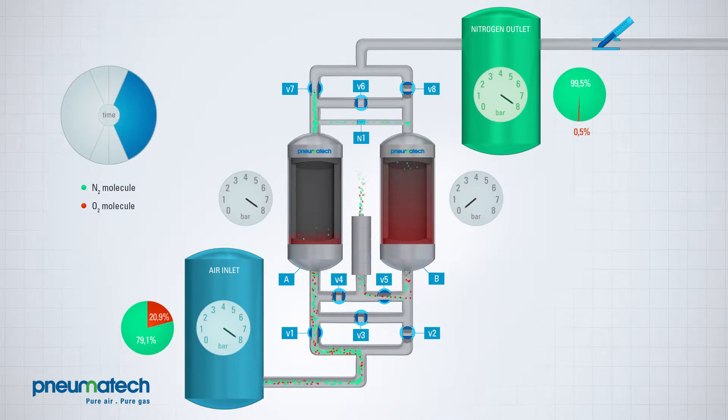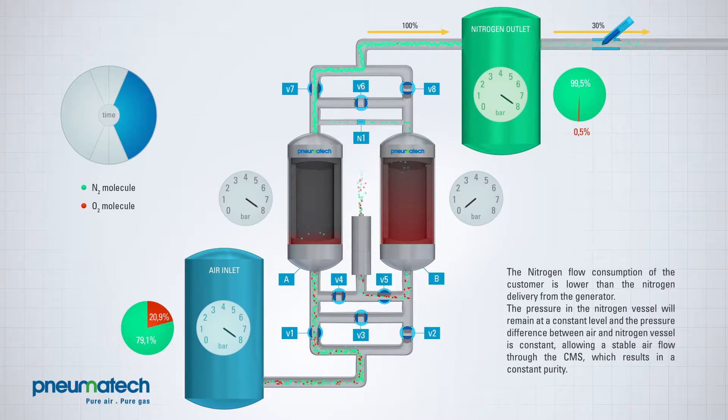The generator is sized to deliver 100% nitrogen to the nitrogen vessel during normal operation. When the customer's application consumes less than 100% of the generator's capacity, for example 30%, the generator is able to maintain the pressure in the nitrogen vessel at a constant level.